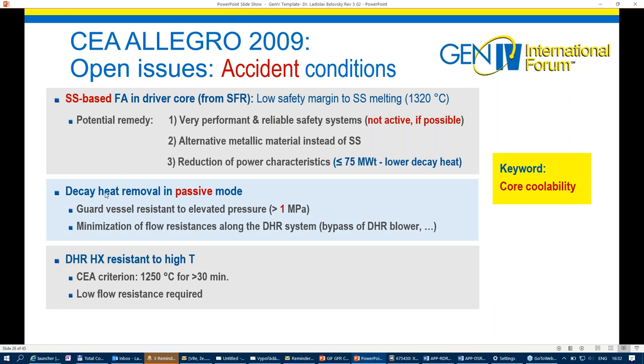One of the issues is the decay heat removal in passive mode. How to ensure the decay heat removal when there is a station blackout and no active systems available? So for example, by promoting the natural circulation in the system, by maximizing the driving force using as high a pressure in the guard vessel as possible.